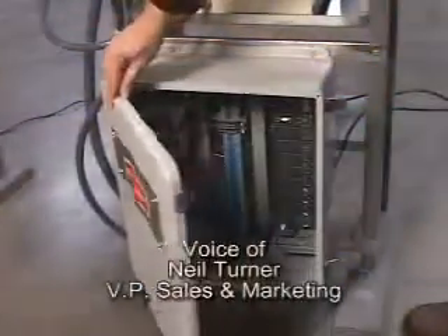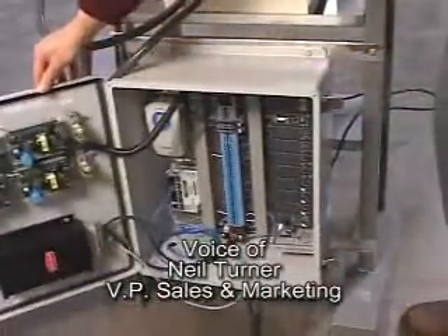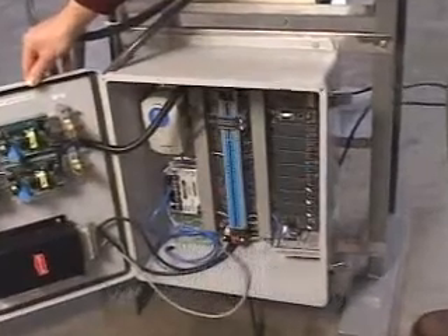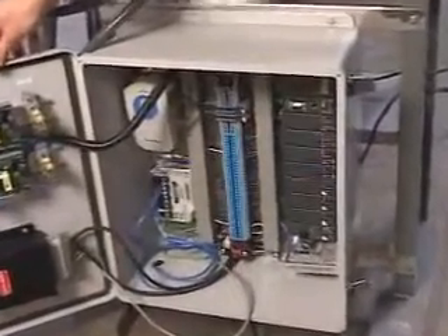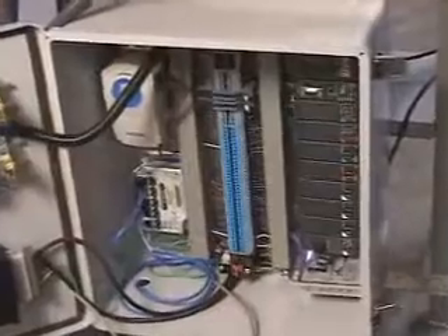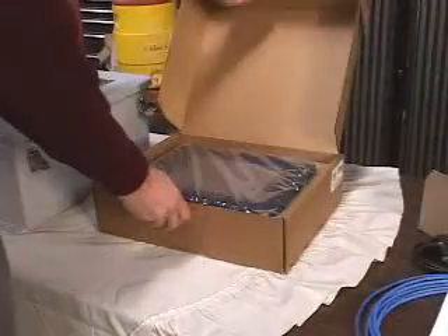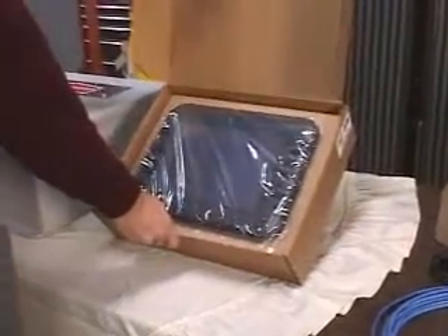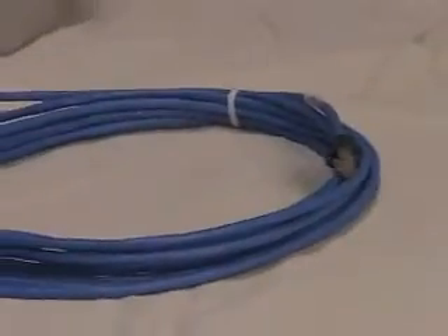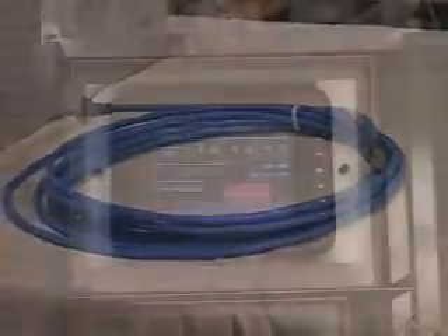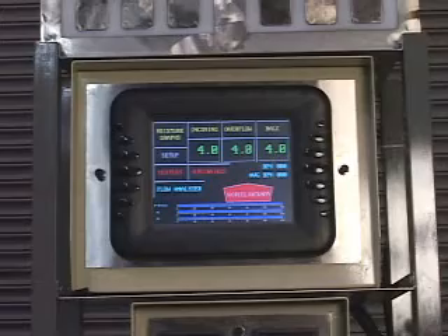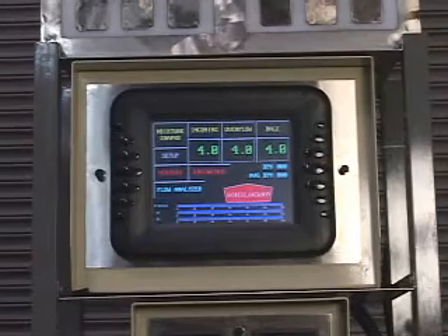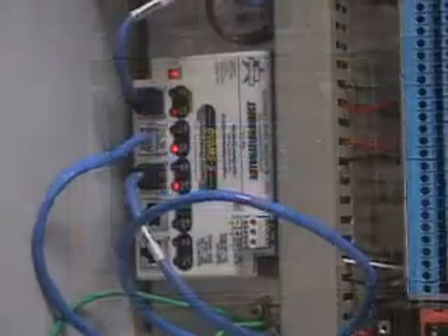The Mirror 2 comes in three pieces. One piece is a fiberglass enclosure housing a PLC control unit, power supplies, and terminal blocks for electrical connections. The second piece is a 10-inch color touchscreen operator panel. The third piece is a conventional Ethernet network cable. The touchscreen may be mounted anywhere in the gin and is connected to the fiberglass control box with Ethernet cable.